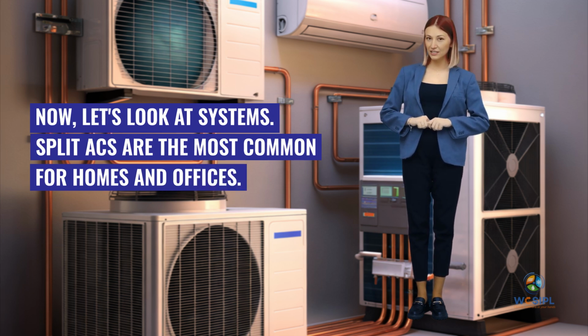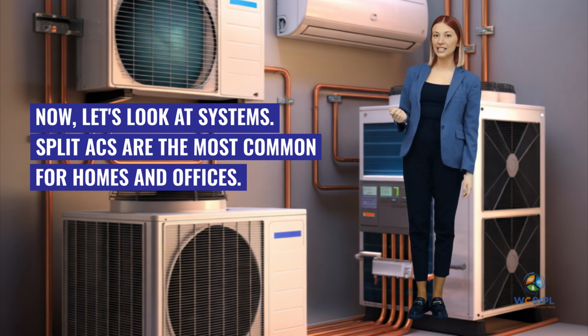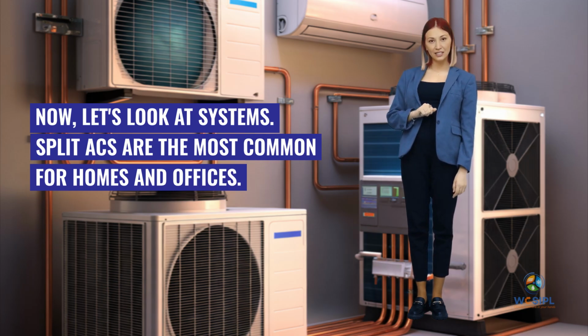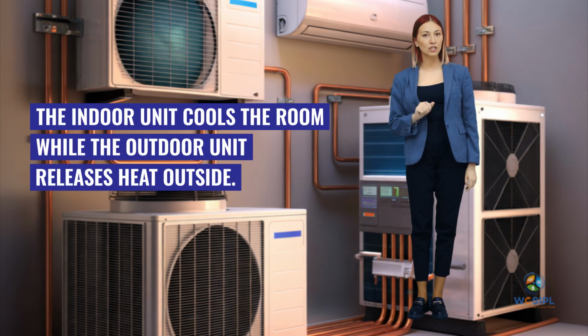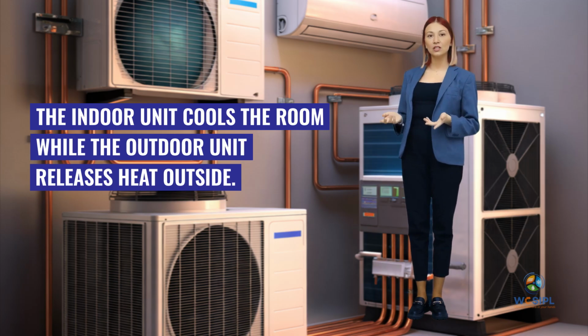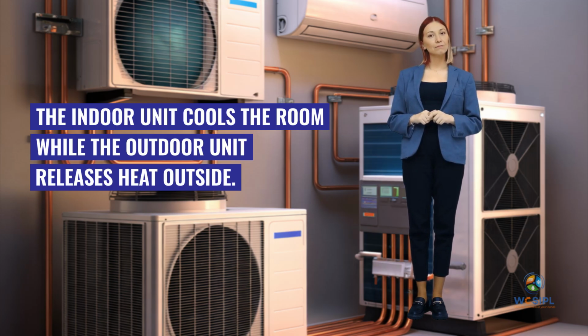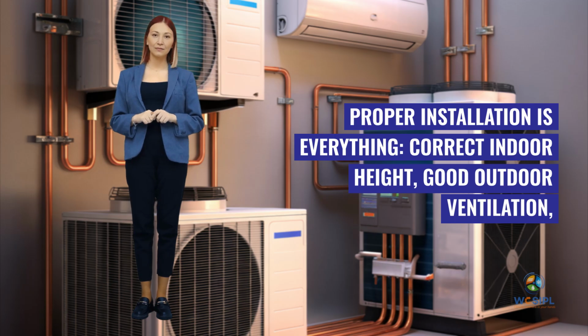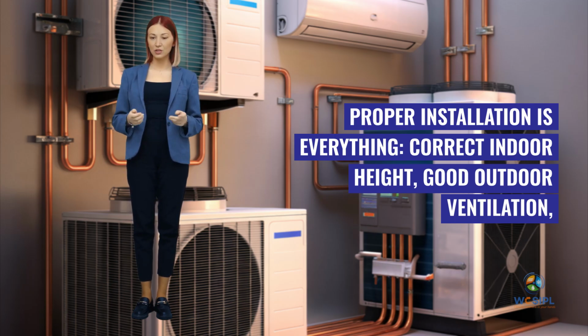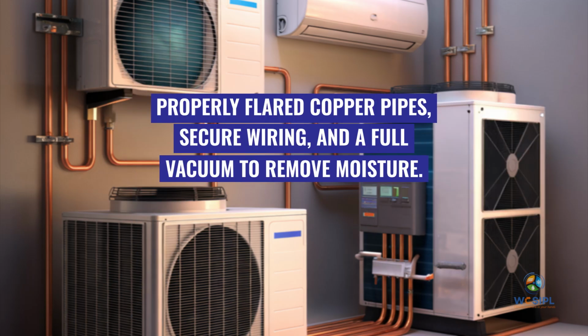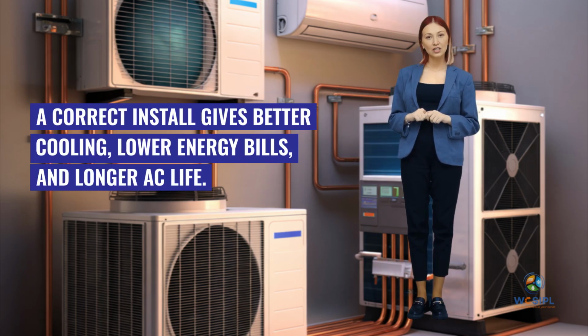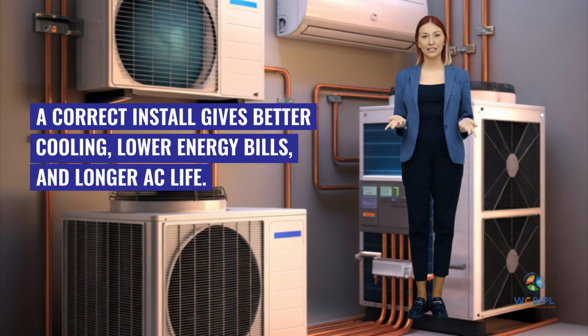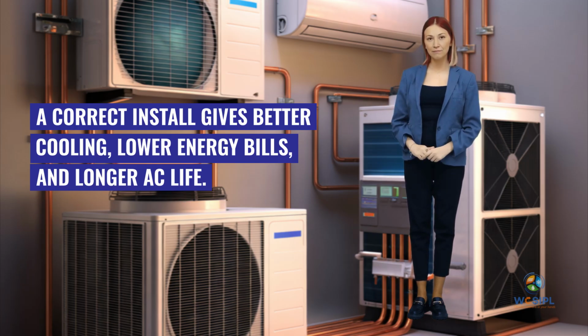Now, let's look at systems. Split ACs are the most common for homes and offices. The indoor unit cools the room, while the outdoor unit releases heat outside. Proper installation is everything: correct indoor height, good outdoor ventilation, properly flared copper pipes, secure wiring, and a full vacuum to remove moisture. A correct install gives better cooling, lower energy bills, and longer AC life.